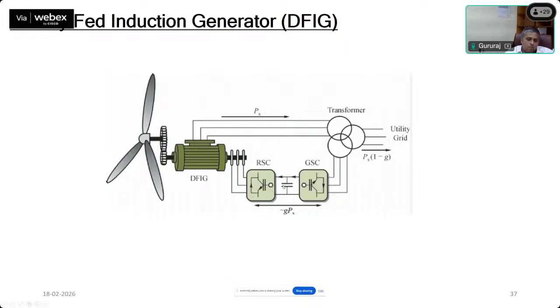And the DC link voltage will drop because power is pulled from this DC side to the AC side, because you need some amount of power which is lacking from the wind system perspective, and that lacking power is pulled from the DC side with the help of this rotor side converter and pumped to the point of common coupling, wherein the power flowing from the rotor side and the power directly coming from the wind plant, both combined together, look like a 50 hertz system being connected to the utility grid, right?